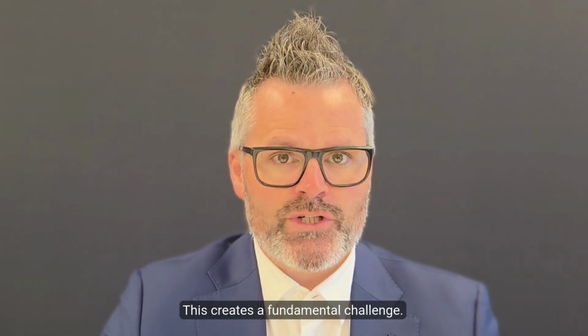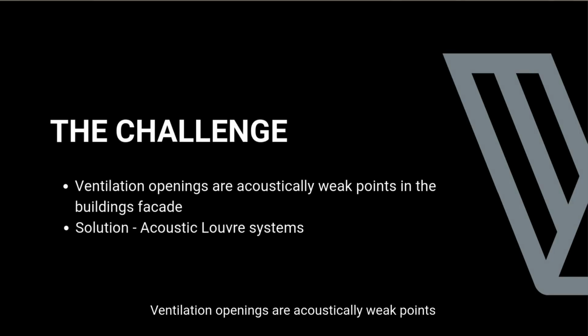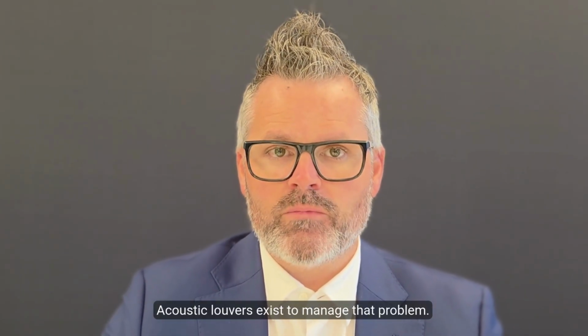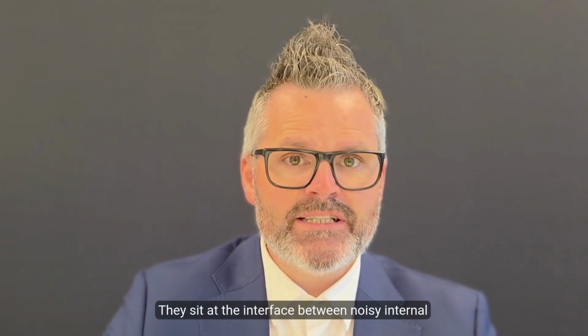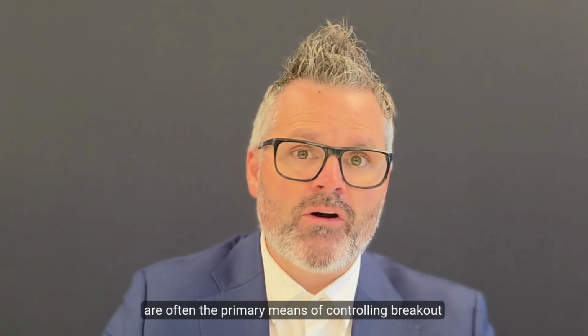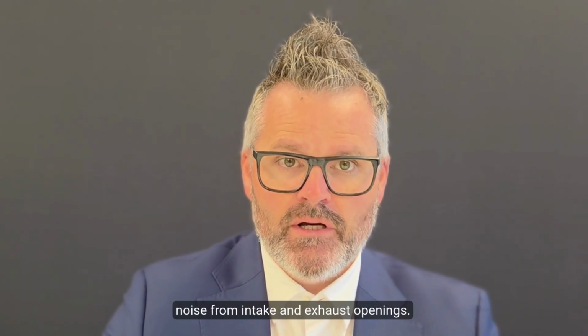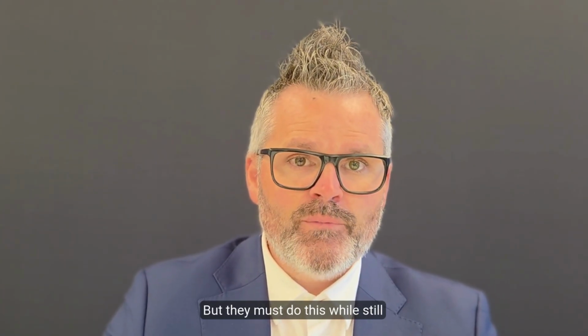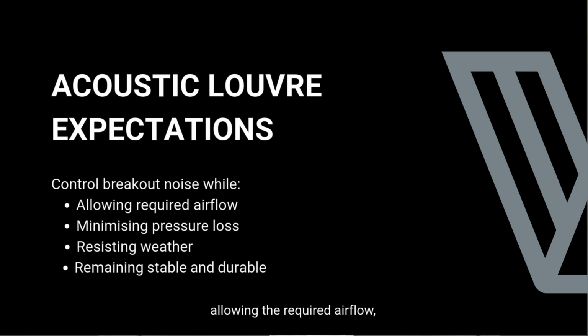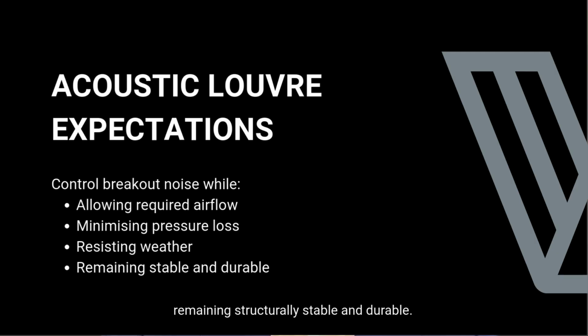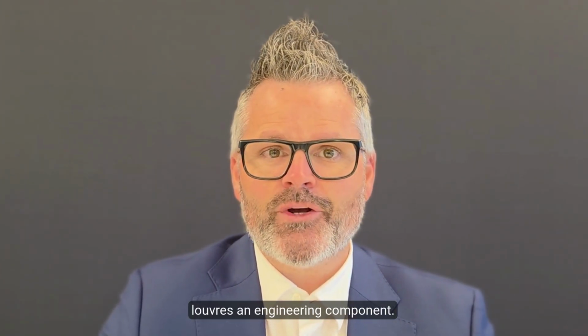This creates a fundamental challenge. Ventilation openings are acoustically weak points in the facade. Without treatment, they allow sound to escape almost unimpeded. Acoustic louvers exist to manage that problem. They sit at the interface between noisy internal plant and the external environment, and they are often the primary means of controlling breakout noise from intake and exhaust openings. But they must do this while still allowing the required airflow, minimizing pressure loss, resisting wind and weather, remaining structurally stable and durable. Balancing those requirements is what makes acoustic louvers an engineering component.